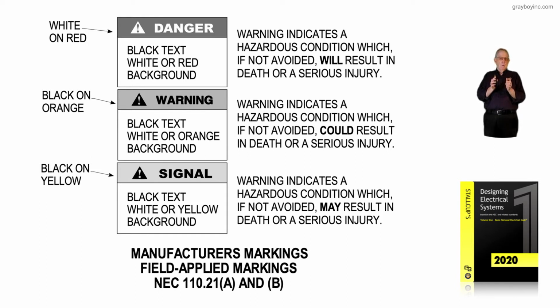cover that you would remove, and that would have danger on it. But if you remove that cover with that orange label on it, and right there were the energized components and conductors, then that should be a red label, because it's immediate danger, imminent danger as soon as you open it up.